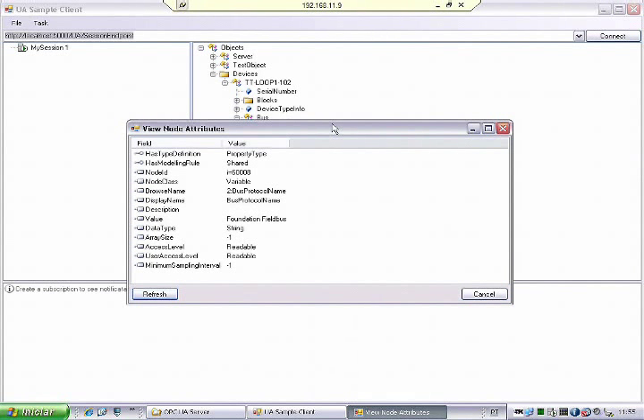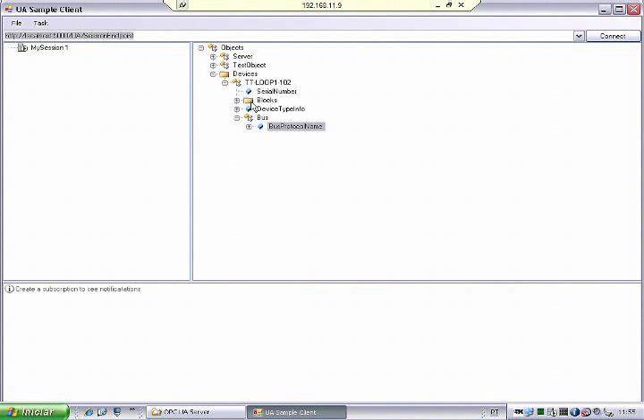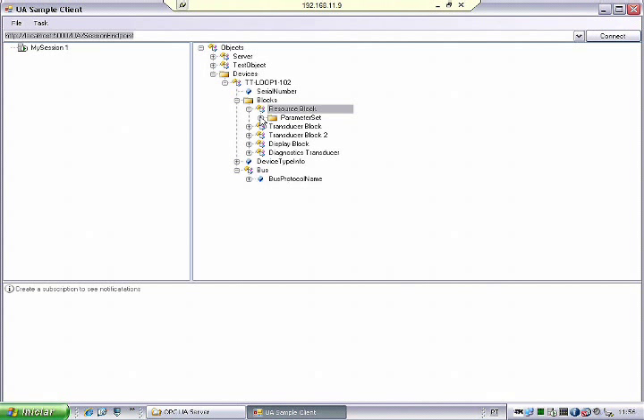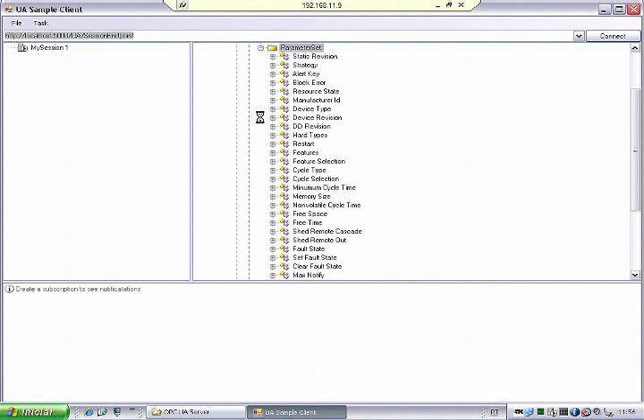The interesting part is when we look at the blocks. These are the function blocks located inside the field device, also supplied by the fieldbus driver. It queries the device and retrieves all its blocks. How those blocks are instantiated is also defined by the information model. All blocks have a folder inside called parameter set, and in that folder you put all the parameters for that block. At this stage, when looking for parameters from the function block, I am looking in the EDD — not the network anymore. The network told me which device and function blocks exist; now I go to the device description.